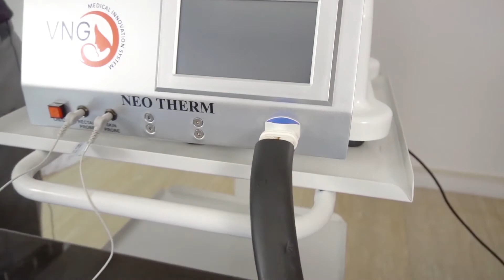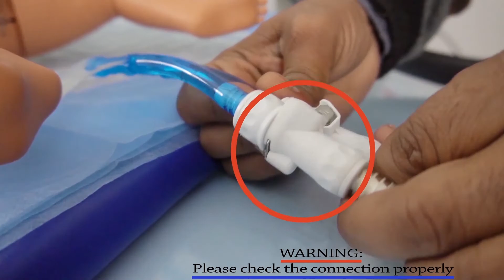Now we will connect the hose pipe. This hose transfers the fluid, in our case water, from the operating system to the mattress. This right here is a reusable mattress. This mattress is used to cool the baby. The baby is placed on the mattress and this mattress is reusable by nature. But make sure that you do not use the mattress more than the prescribed safe therapy limit. Also, do not use it if it is damaged or in case of leakage or inflammation. Contact the sales team immediately and get your mattress replaced in case of any such observation.